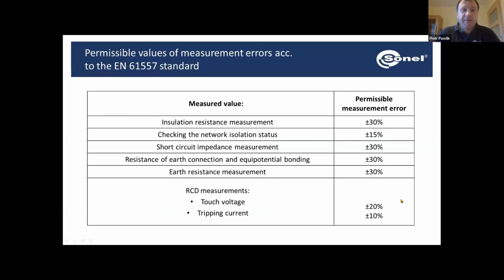Okay, so we have made all our measurements. Now let's look at our measuring equipment. Once we look into the IS 732, it says that the meters should comply with the IEC 61557. And the standard is a multi-sheet standard. Each sheet describes different types of measurements. But what is important to us as test technicians, this standard describes the maximum permissible error.